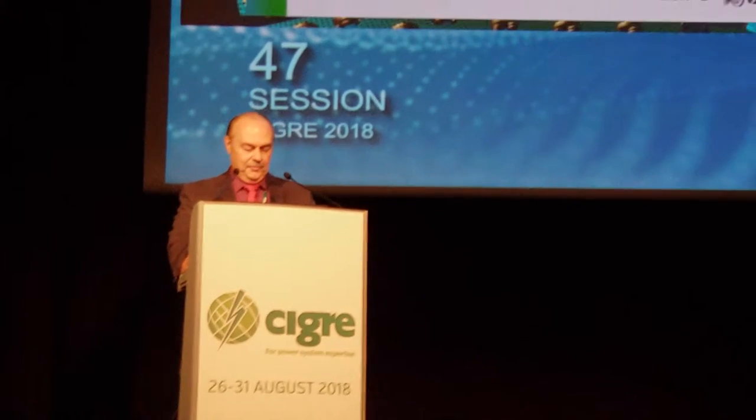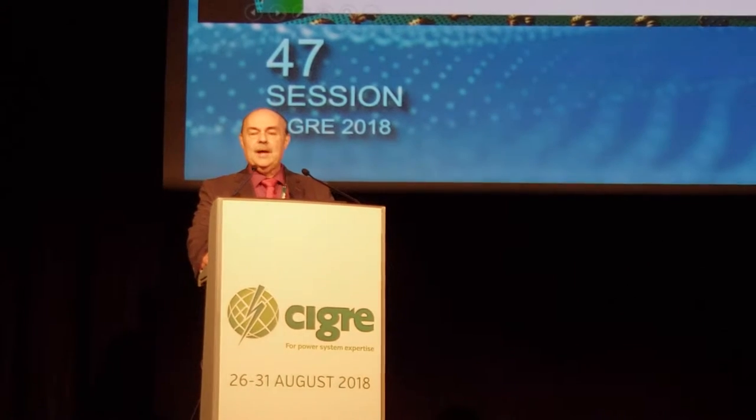Tests performed at Cepel Eletrobras Research Center in Rio de Janeiro for such 345 kV switches show two different situations: interruption without fast arc extinction, and interruption with fast arc extinction. Let's see the short videos of each test.